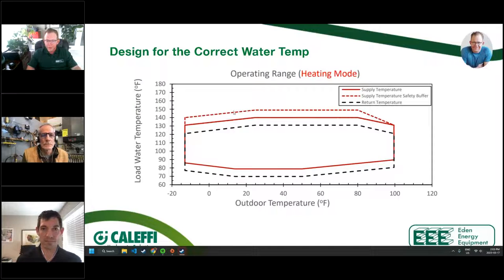And you can see that if we get above about 143 degrees, we are now outside of that safety buffer for that compressor. So, again, look out for yourself, look out for your installations. Don't design these. Even if this was 150, I would again ask, why are you redlining this appliance? Whatever this number is, don't go near it. You'll see that the supply temperature we're specifying is 130, right? So anything within this red box here would be more ideal.